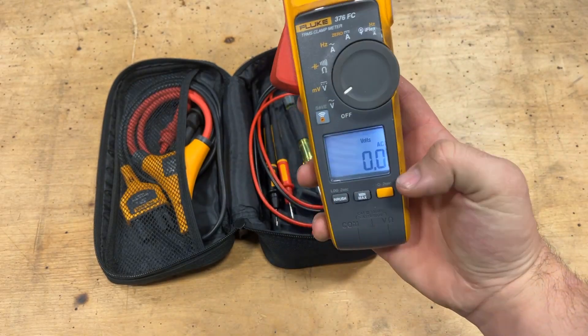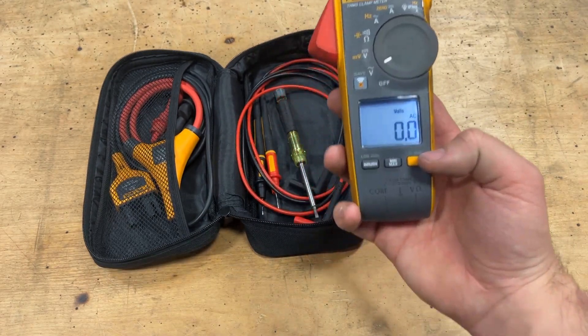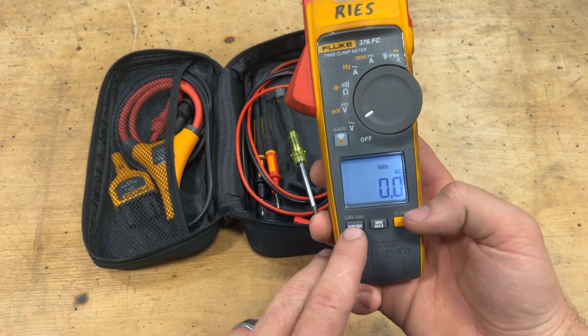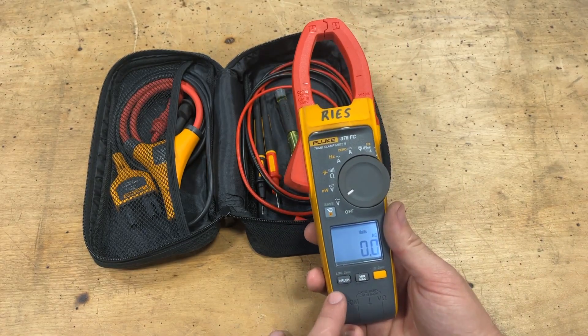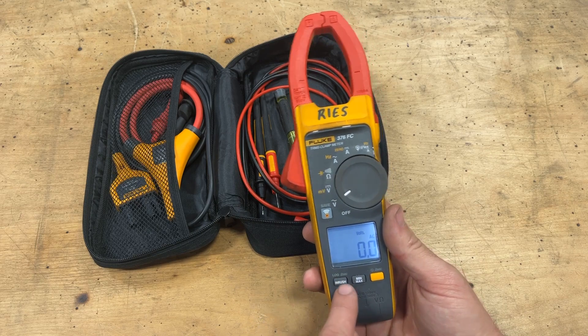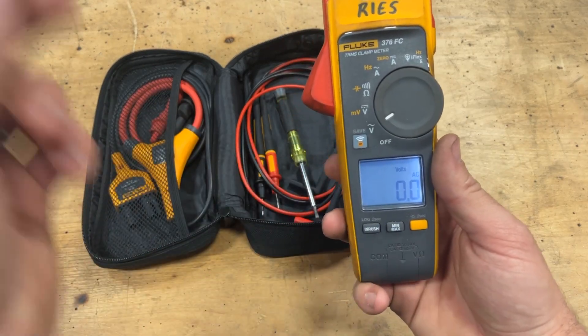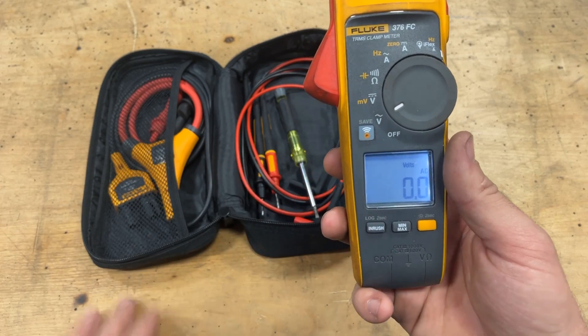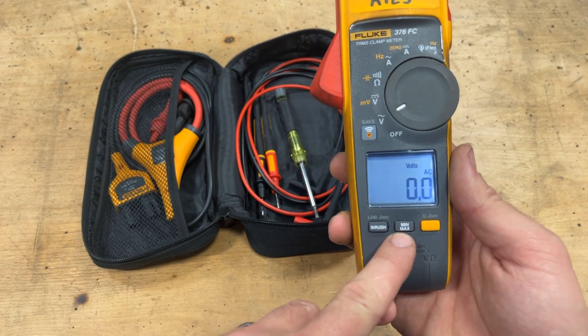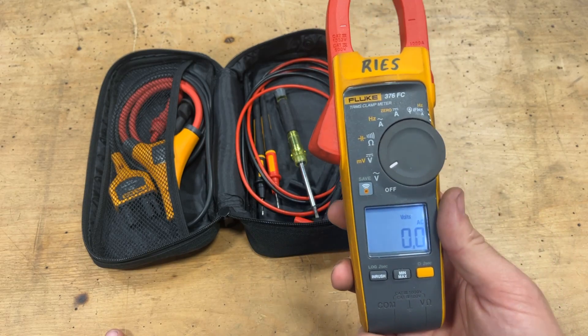Hold this button — backlit LCD screen. Can't beat that because if you're in this industry, you're never in a nice place to work. It has a function specifically for picking up inrush on AC motors. This is super nice because you don't have to wait and watch for that peak current — if you set this and turn on your motor, it'll automatically save and display the peak inrush current so you know what you're looking for. On the same note, you can set the min-max setting, so whenever you're running a diagnostic through a system, this will tell you the minimum and maximum voltage you read during that test.